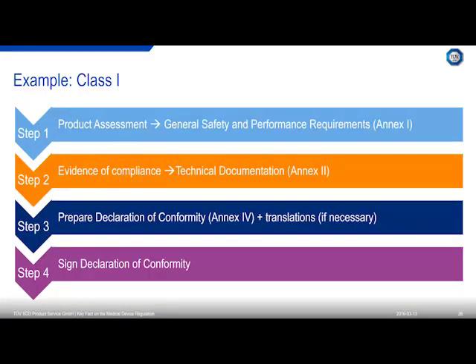I don't say that's it in terms of registering the device, because that's something that needs to be done under EUDAMED, which is not yet in place and where we don't yet know how this will be handled in future. We can only say that once EUDAMED is in place, we will know how to register these devices. What you of course can do is ask your competent authority what to do with a class 1 device, because basically you could register a class 1 device by law as of today. But as far as I know, no competent authority is able to support this.